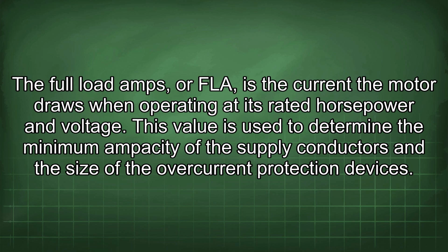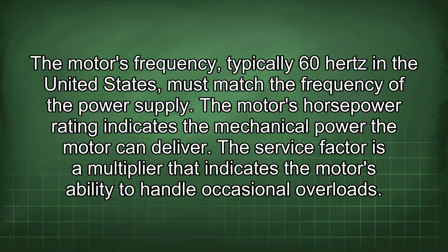This value is used to determine the minimum ampacity of the supply conductors and the size of the overcurrent protection devices. The motor's frequency, typically 60 Hz in the United States, must match the frequency of the power supply. The motor's horsepower rating indicates the mechanical power the motor can deliver.